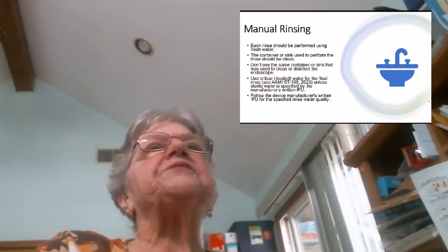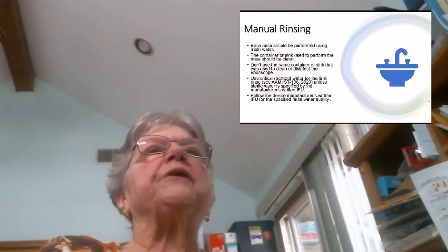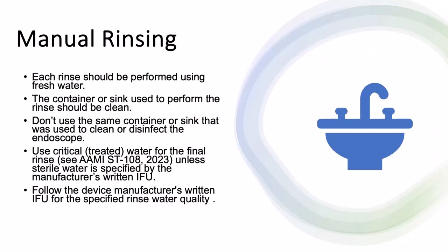When you manually rinse, each rinse should be performed using fresh water. The container or sink used to perform the rinse should be clean. Don't use the same container or sink that was used to clean or disinfect the endoscope. Use critical water for the final rinse unless sterile water is specified by the manufacturer's instructions, and we do have some that are telling you to use sterile water for the final rinse. And follow the device manufacturer's written instructions for the specified rinse water quality.